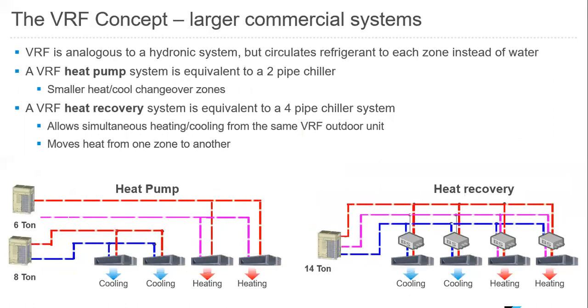So we have 2 different types of VRF systems. We have a heat pump. Think of a 2-pipe chilled water system. With our heat pump VRF system, all of the indoor units will be in the same mode at the same time. They'll either be in cooling or in heating. In this example, I have a 6-ton heat pump with 2 indoor units downstream, and they're in heating. Just below that 6-ton outdoor unit, I have an 8-ton outdoor unit with 2 indoor units downstream in cooling. So all those indoor units on that 6-ton system are going to be heating when we call for heating. And on that 8-ton system, we're calling for cooling, so all those indoor units downstream are going to be cooling.